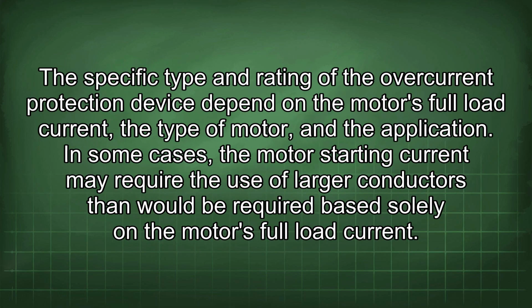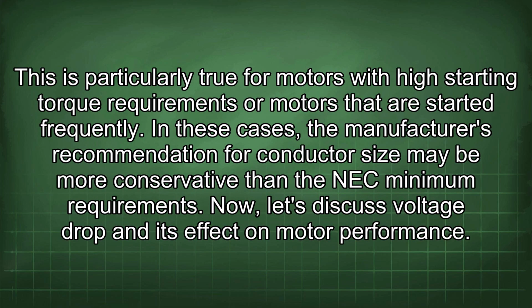The specific type and rating of the overcurrent protection device depend on the motor's full load current, the type of motor, and the application. In some cases, the motor starting current may require the use of larger conductors than would be required based solely on the motor's full load current. This is particularly true for motors with high starting torque requirements or motors that are started frequently. In these cases, the manufacturer's recommendation for conductor size may be more conservative than the NEC minimum requirements.